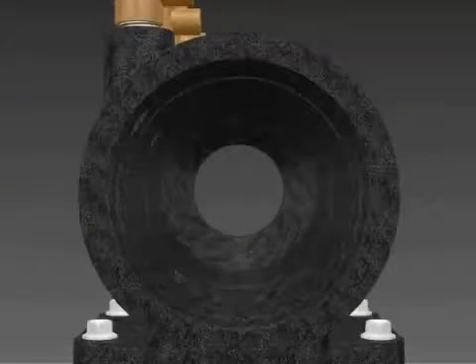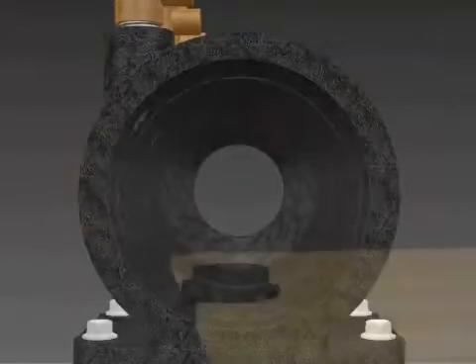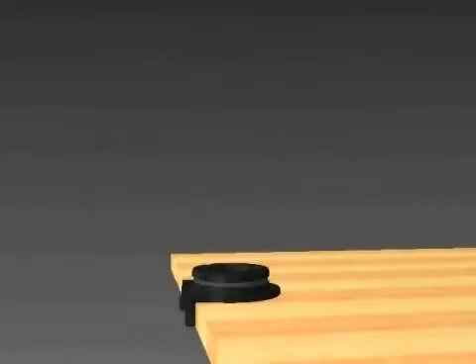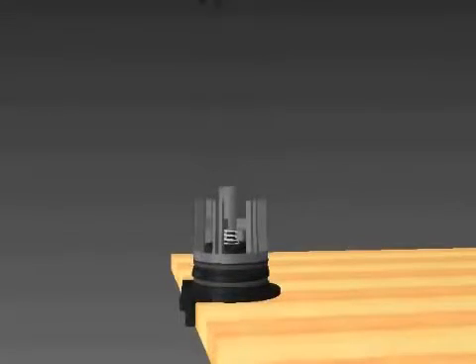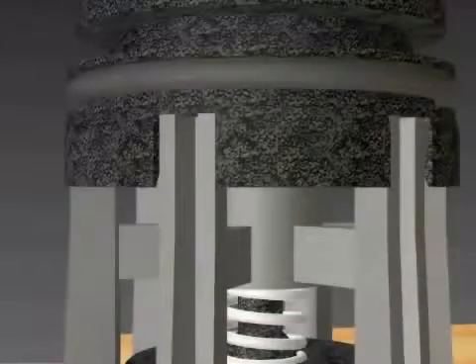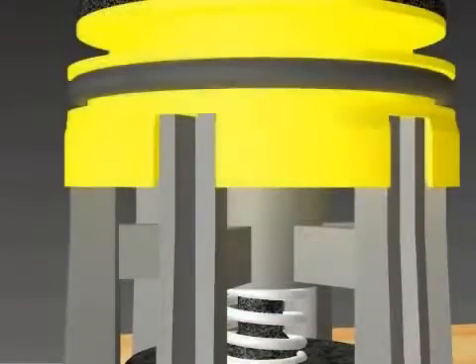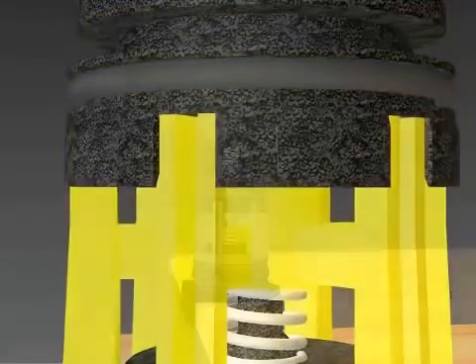Wipe clean and inspect the inside of the housing. Place the sleeve on a flat surface with the bolt tab hanging off the edge. Stack the number 1 check and then the number 2 check on top of the sleeve. Make sure to line up the notches in the number 2 check with the number 1 spring retainer.